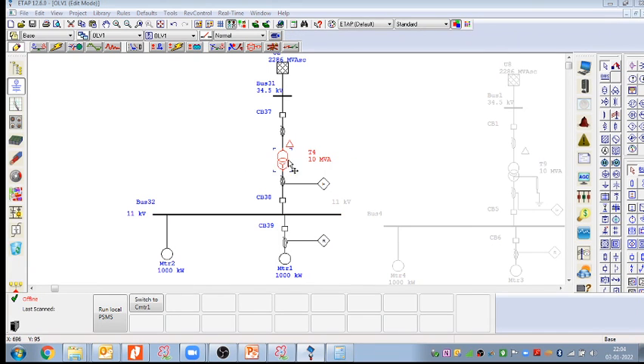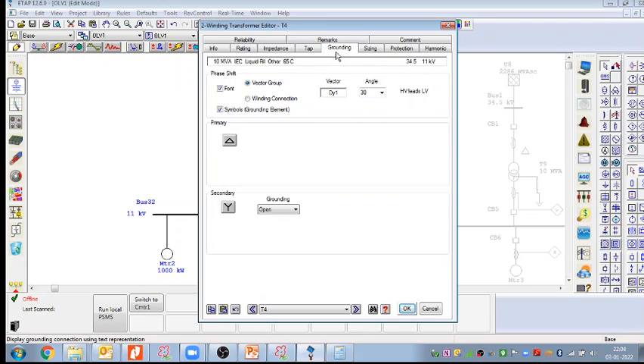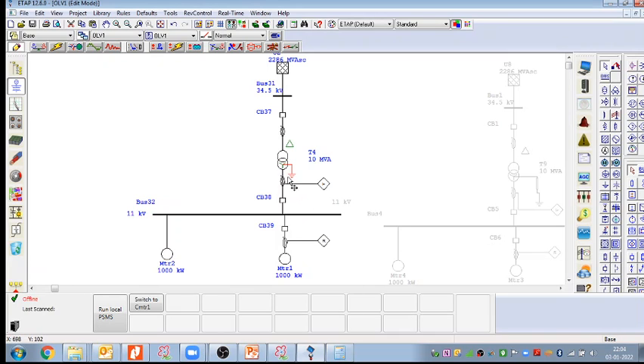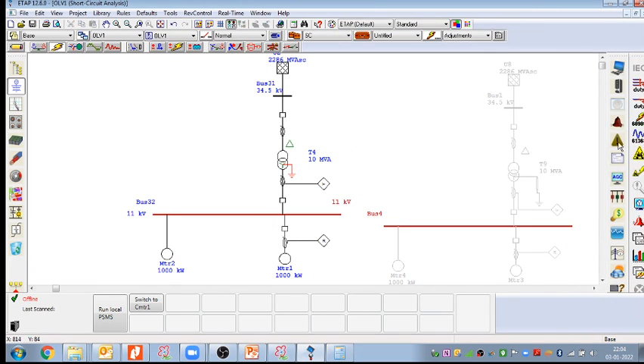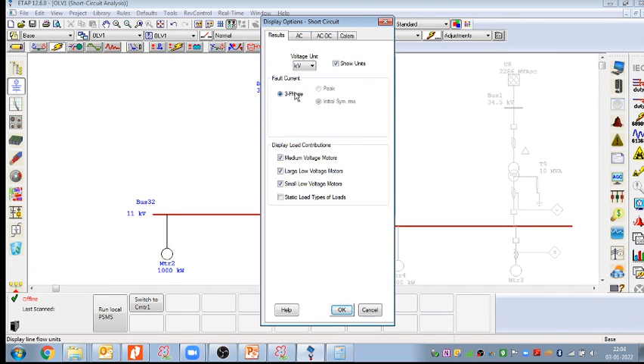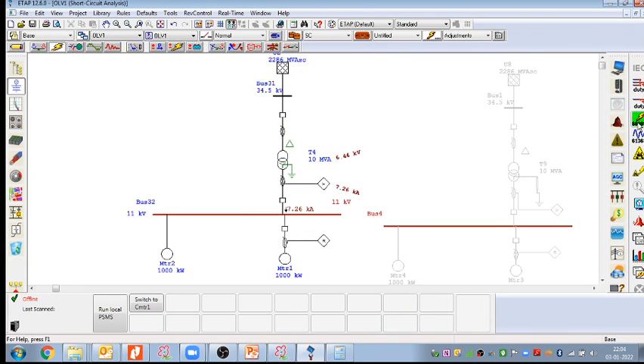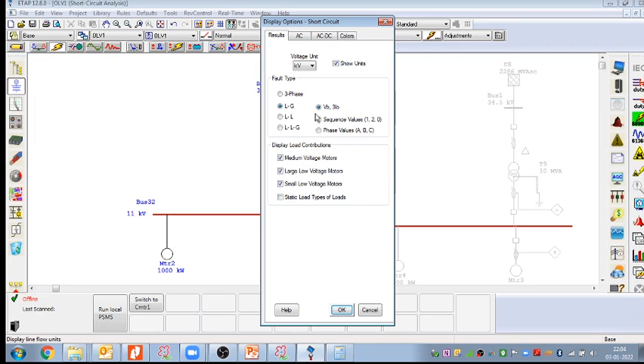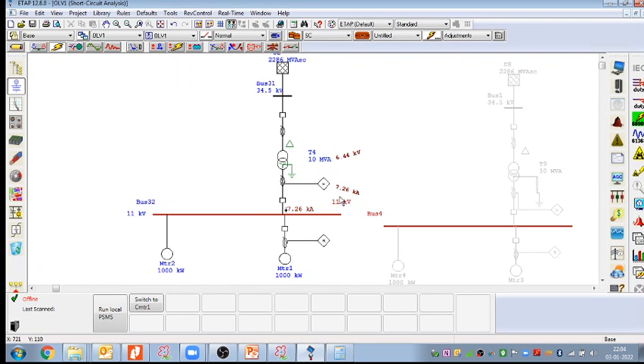What I do here, I again go to the transformer, grounding tab. Here let me take solid grounding. I'll go to the other groundings also one by one. Let me go solid grounding. Now here we have done it. Now if we do the fault current analysis, L2G we have already selected here. Now in that case you can see this current is coming. Initially it was 0 kiloampere, but now it is coming 7.26 kiloampere, right?